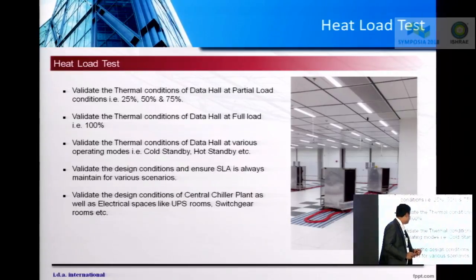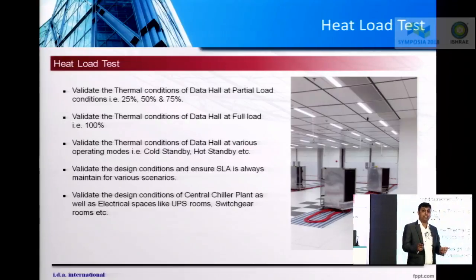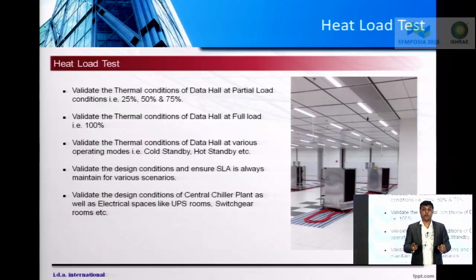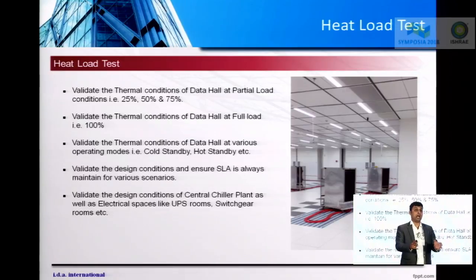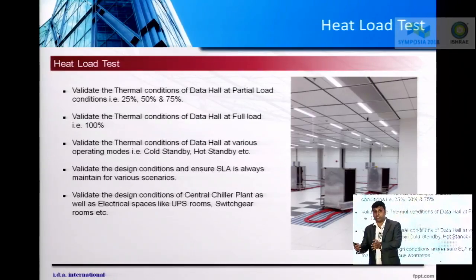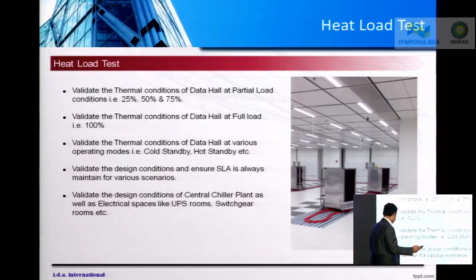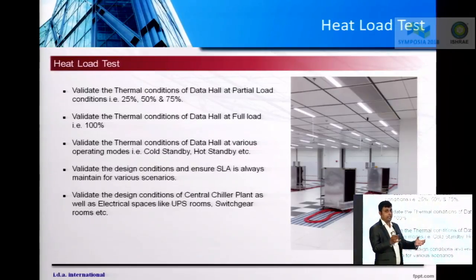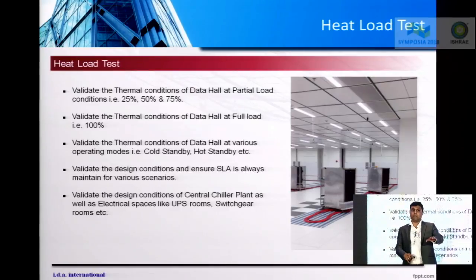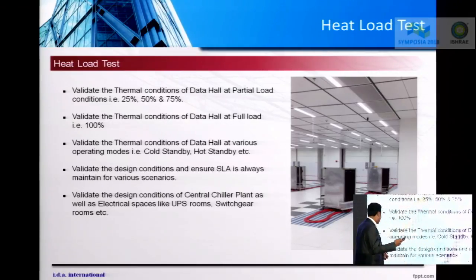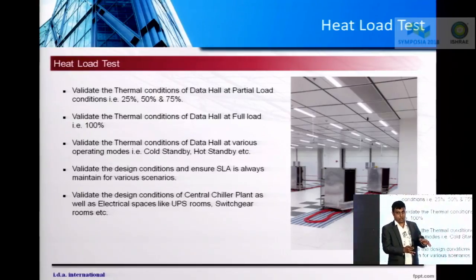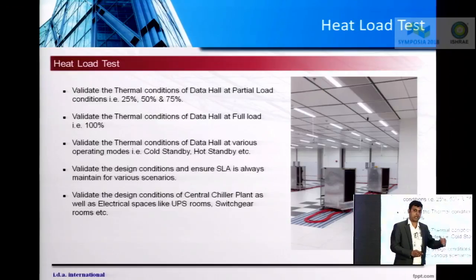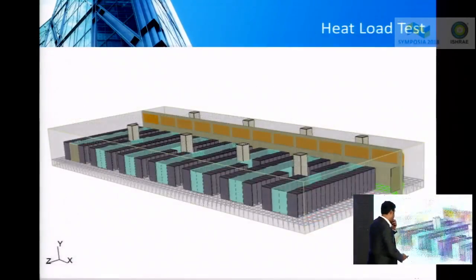The second thing is, I have to verify the thermal conditions of the data hall during different modes of operation. It could be a hot standby mode, or it could be a cold standby mode. We'll see how it works. And throughout the heat load test, we have to ensure that the temperature and the relative humidity are not crossing the SLA limit provided by the owner. And of course, when you do a heat load test, you have to keep a very close eye on the chiller plant, of how the chiller plant behaves when you start loading your data centers. So let's have an example here.